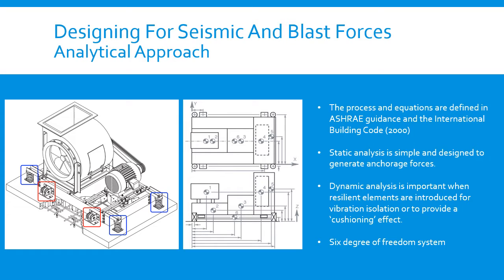Static is simplistic but suited to statically mounted cases where equipment is rigidly bolted. The nature of the forces will dictate the extent of anchorage required to prevent overturning, pivoting, swinging, etc. It's important to note that anchorage into structure is only as good as the structure itself, which also needs to be reviewed.